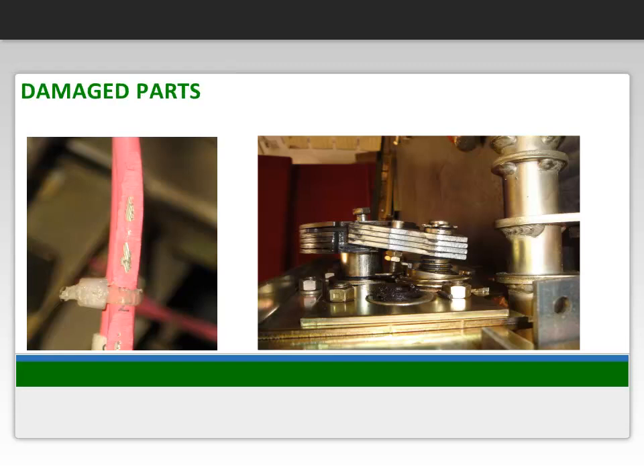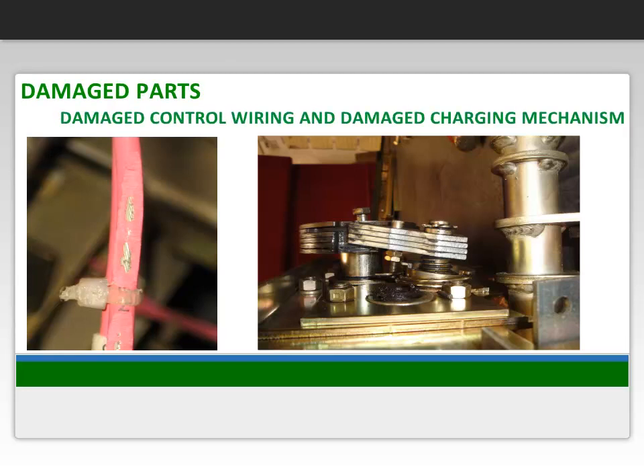Here are examples of damaged control wiring and a damaged charging mechanism. The damaged insulation on the control wiring may not be as obvious, so careful inspection of all wiring is necessary. The charging mechanism is more apparent because of the broken plates. Both could cause major headaches for the user at a later point.